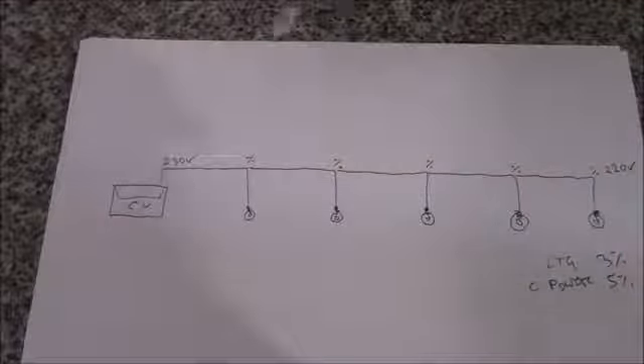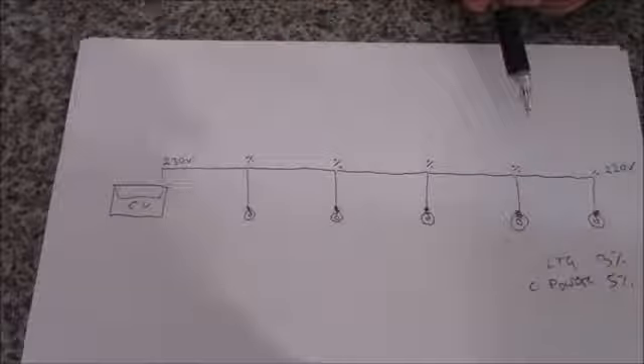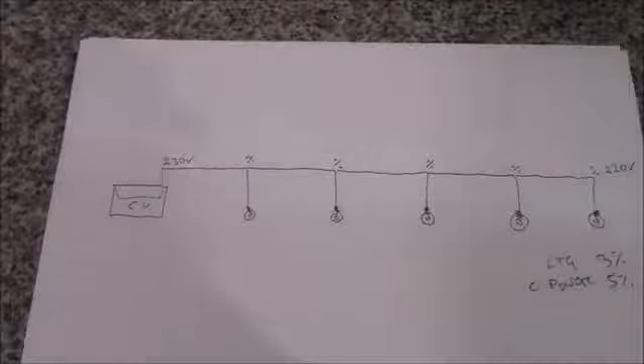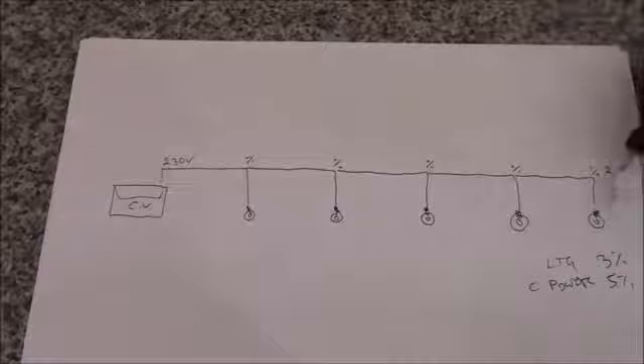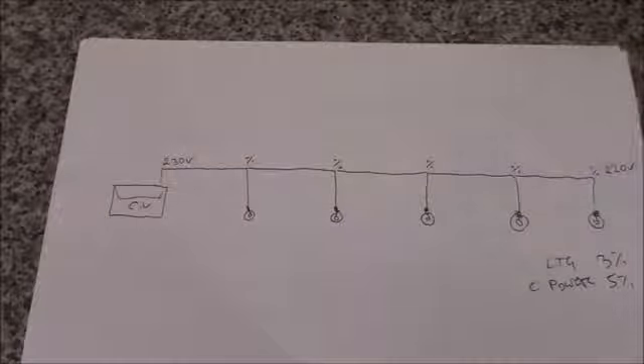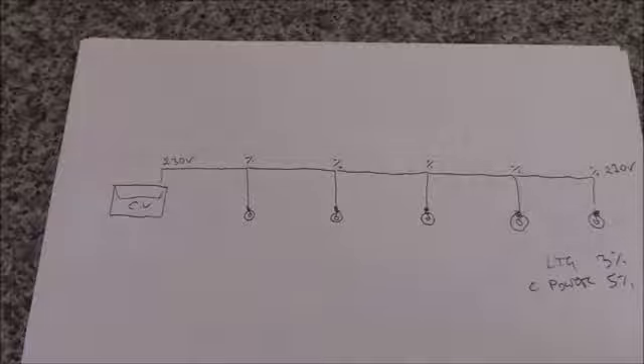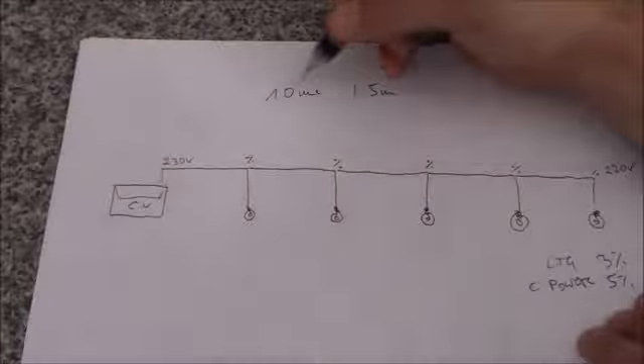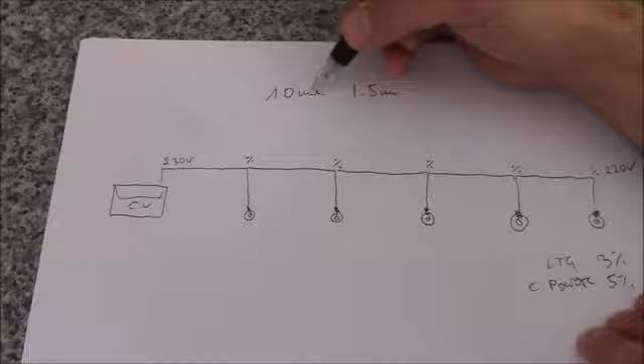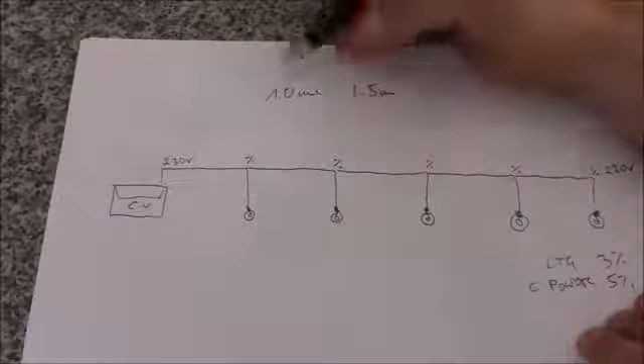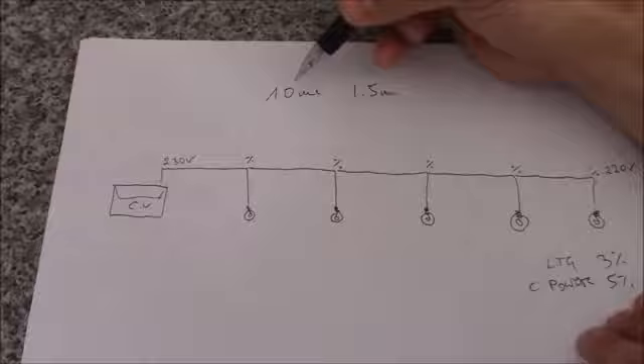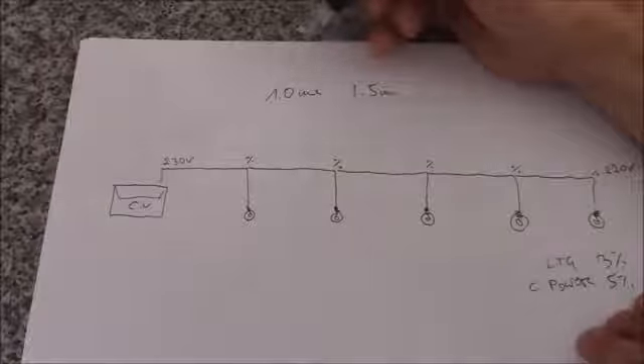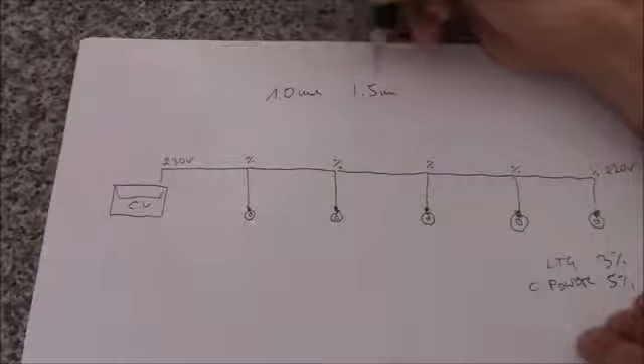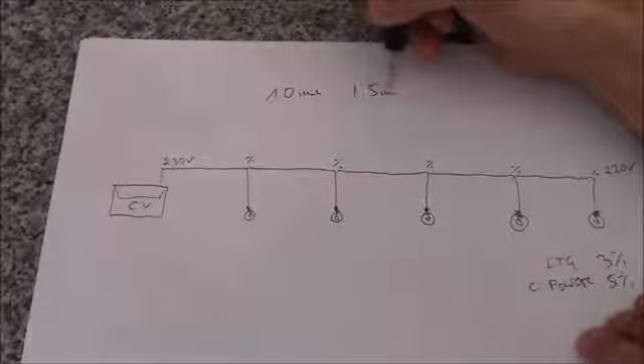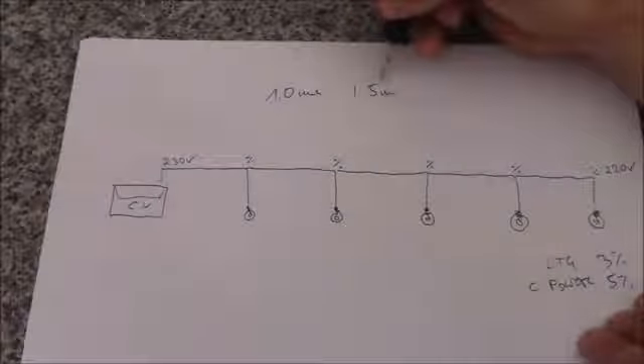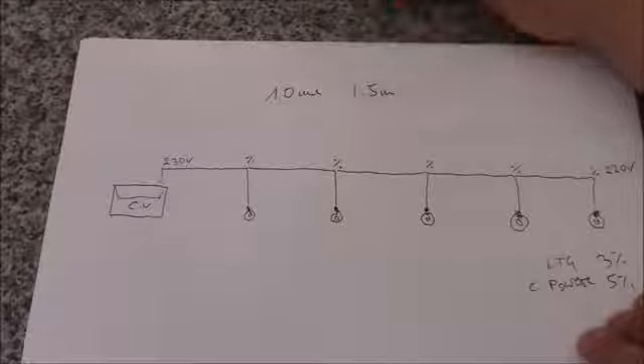Basically a cable that is too long can cause too much voltage loss, and then the bulbs will be flickering or the items not working properly at the end. So for lighting circuits at home you use 1.0 millimeter cable, but if you've got a large house and one circuit serves a few rooms, kitchen, a few bathrooms and other stuff, then I would consider using 1.5 millimeter cable. This cable is a bit bigger and the voltage drop will be less.